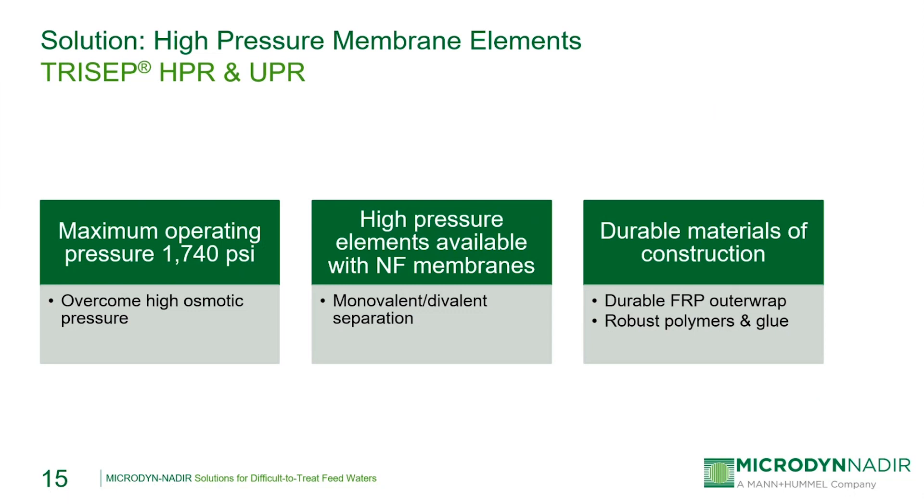The Trisep HPR and UPR line can be used for industrial and seawater applications where high pressure operation is required to overcome high osmotic pressures. For MLD and ZLD systems, this means that TDS concentrations of 100,000 ppm or greater can be reached, resulting in higher recovery from the membrane system and less expense on evaporation and crystallizers downstream. These membranes are also available using any of our nanofiltration membranes for situations where separation of hardness ions from high TDS brine solutions is required. The Trisep HPR and UPR series consists of a durable fiberglass outer wrap and robust polymers and glues that can handle operation at these high pressures without any loss of integrity.